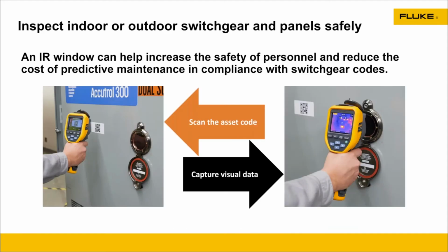So one of the fault conditions we talked about earlier was potentially taking a panel door off, and that could cause an arc fault or an arc blast. What if you had an IR window? What if I was able to take a thermal imager and look through this device and scan all that safely? I didn't have to put my PPE on. All I had to do was open up the window door and scan with my thermal imager. Again, another safer way to do your job and make those measurements. Some of them you can even scan an asset code and then data log that, capture your image, and put it into a profile. Again, a safer way of making those measurements.